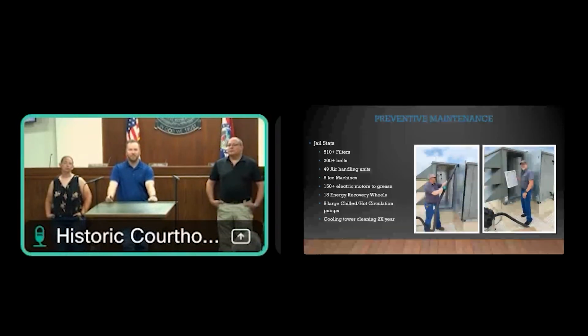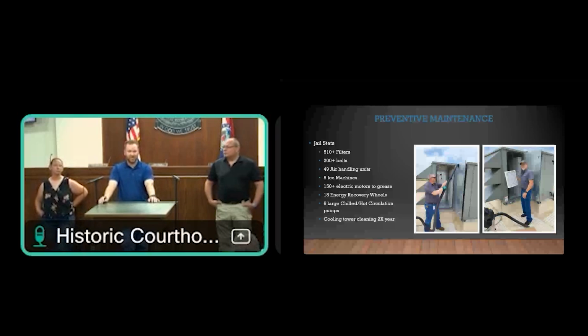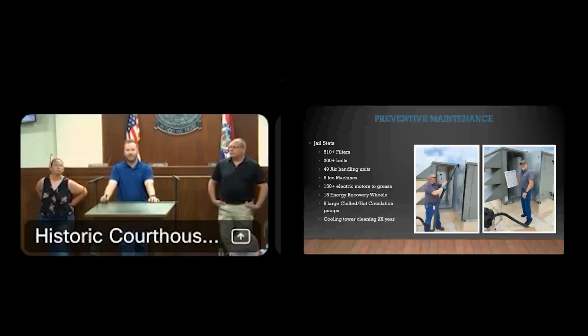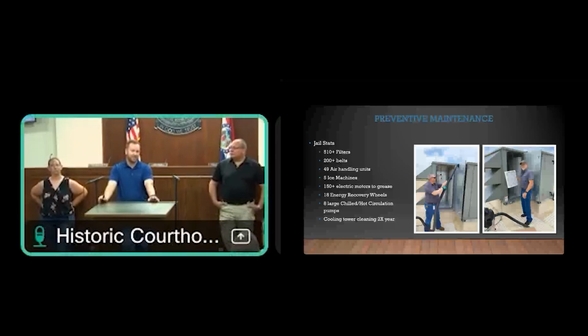And then, like Franz said, our preventive maintenance team is vital at the jail. The pictures here, Rob's on the left and Andrew's on the right. They're replacing filters, and then they also vacuum the units. And just some of the stats at the jail alone, we have over 510 filters, and most of those do get changed monthly. 200 belts, 49 air handling units, ice machines, electric motors that need grease, ERU wheels that need cleaned periodically, large circulation pumps that we clean the strainers on, and then we also clean our cooling tower twice per year.